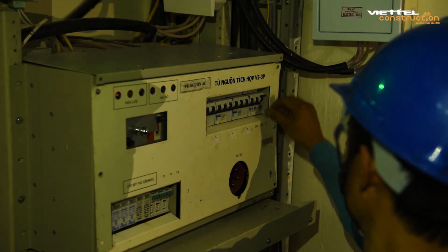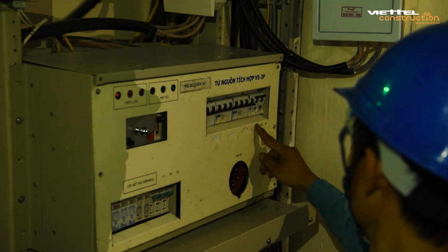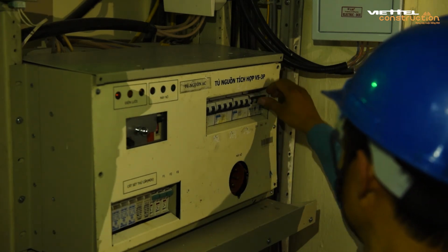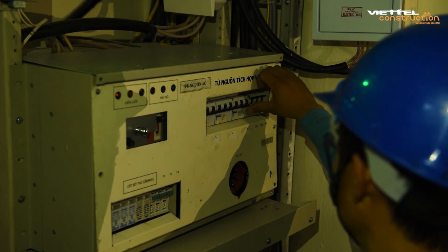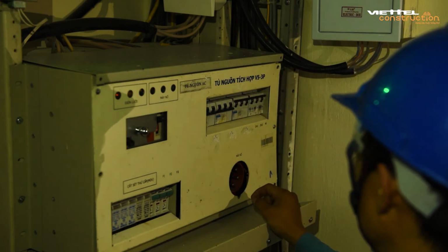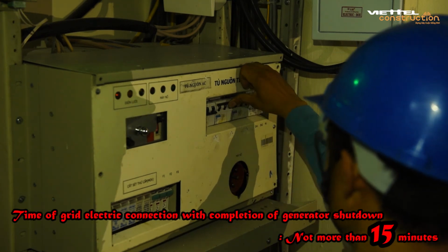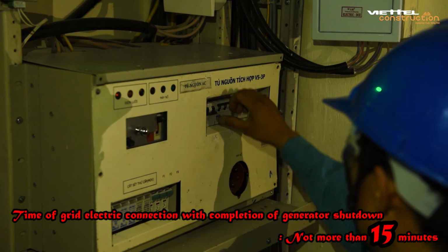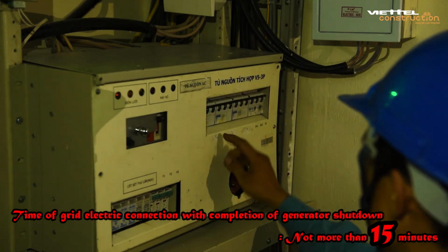Turn on all the CBs that supply power to the station, such as lighting, air conditioners, and DC power cabinets. Turn off the generator after idling and clean up the tools. The time from grid electric connection to completion of generator shutdown should not be more than 15 minutes.